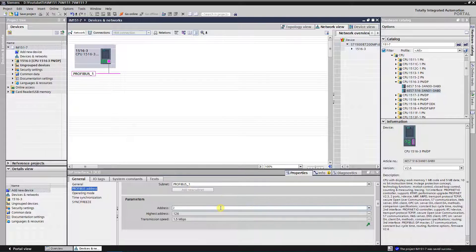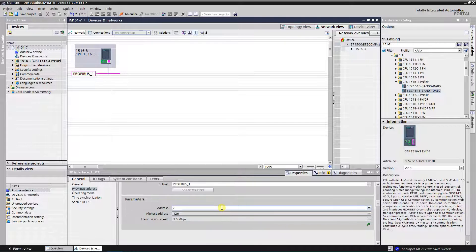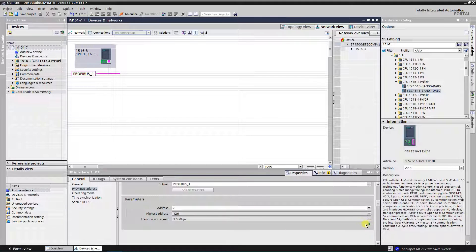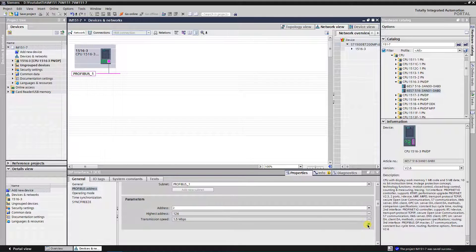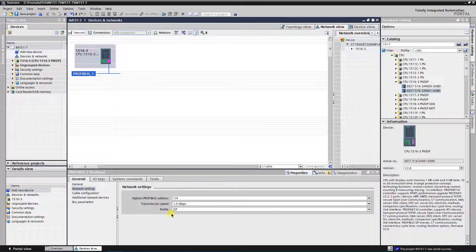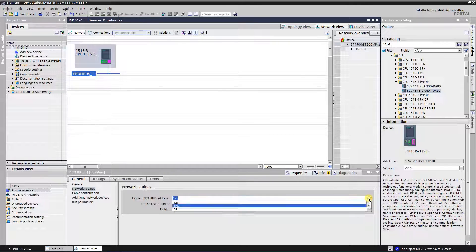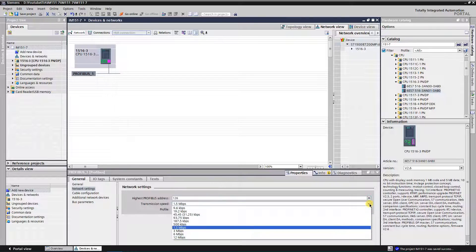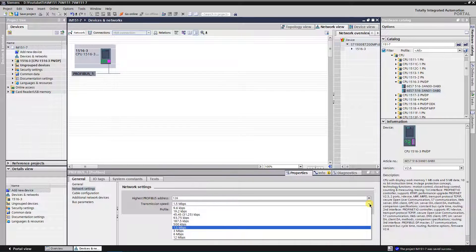If you want to change the parameters of DP master system, you can click green arrow. It will open DP master system parameters window. In the network settings you can change highest PROFIBUS address, transmission speed and profile of your DP master system.